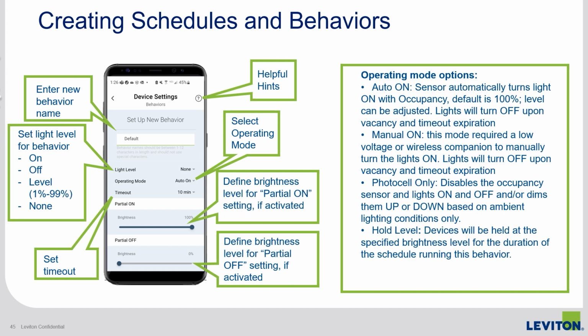If a partial on level is also selected, it will go to that level after the next event, vacancy, then occupancy. Next is Off. Just like turning the lights on, they can be off when the behavior starts. Next is the operating mode, which is just like the standard operating mode selected on the main settings page. However, this mode is specifically for the behavior. The operating mode options are Auto On.